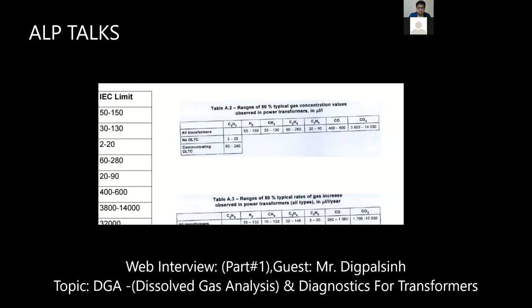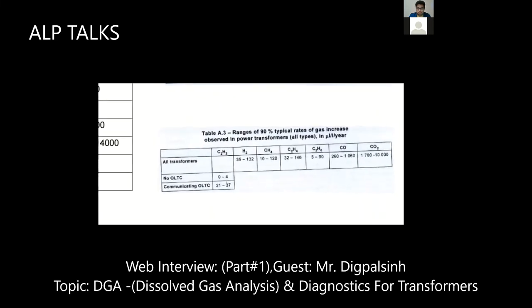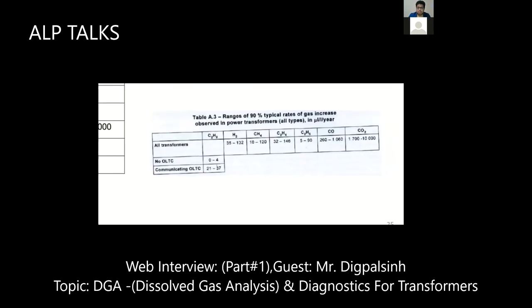This I have copied from IEC, which I have already discussed. The IEC has given one beautiful chart of what the rate of rise in ppm per year should be. You can say after 5 years, H2, some stray gases are there, as we discussed. H2 will be produced by default even if there is no fault, once you use the transformer for 5 to 6 years. And in case some overload is required by the utility, the transformer is overloaded. At the time of overload, the temperature goes beyond the designed value. So during that 1 or 2 hour period, some gases will be formed. And once a minor amount of gas is formed, it goes for chemical reaction and produces gas exponentially. So this is the ppm range per year. You can say 90% typical rates of gas increase observed in power transformers. These gases increase in these numbers per year.